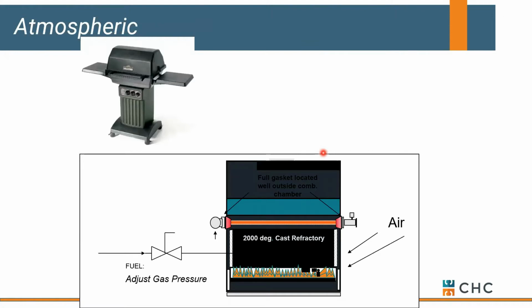Let's talk about some different categories of boilers. Old school might be an atmospheric boiler. One way to think about that is kind of like the barbecue on your back deck. You typically control the burners simply by controlling how much fuel is leaving your propane tank. You do the same thing on a boiler. We control the fuel supply, but the air simply comes from the surrounding space. We generate hot flue gas, and either we're cooking burgers on our heat exchanger, or in this case, we flow water through it, and we're picking up heat and sending hot water out to our system. The rest of that hot flue gas carries over across our heat exchanger, and we typically collect it in a vent or flue, and get it safely out of our mechanical room or out of the building, okay?